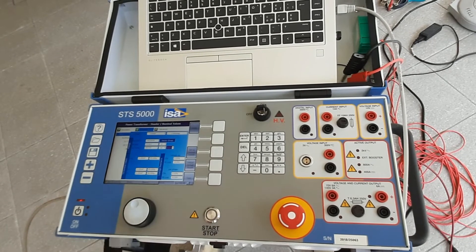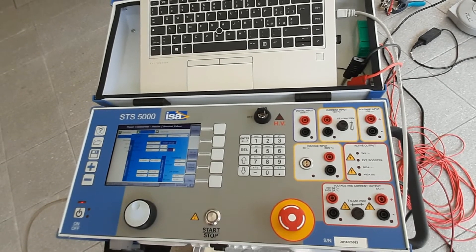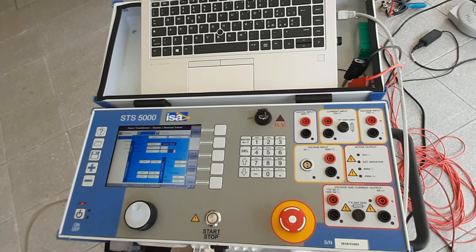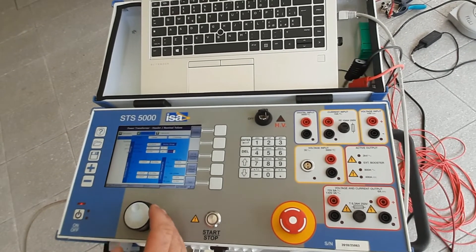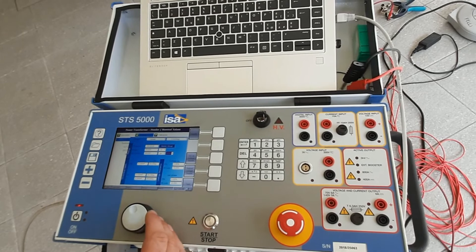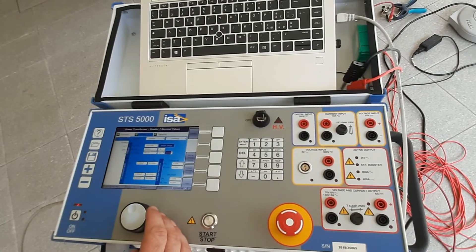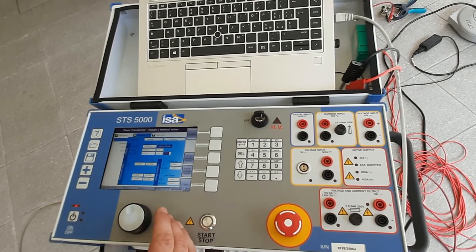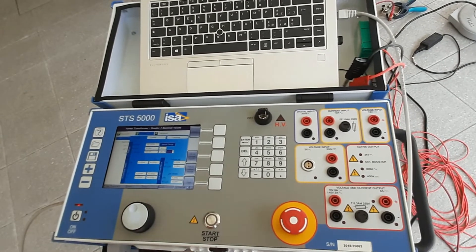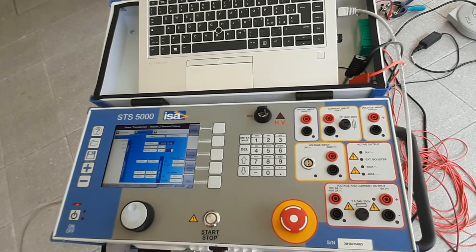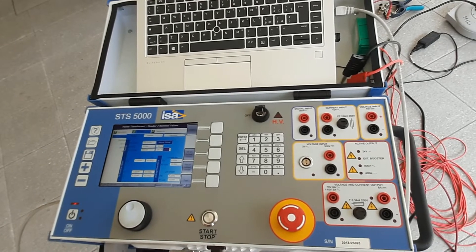So these are my settings, and in order to do a proper ratio test, this needs to be correct. Otherwise the results will be all over the place. Another thing you have to ask yourself is do you have an online tap changer, on-load tap changer, or do you have a de-energized tap changer?